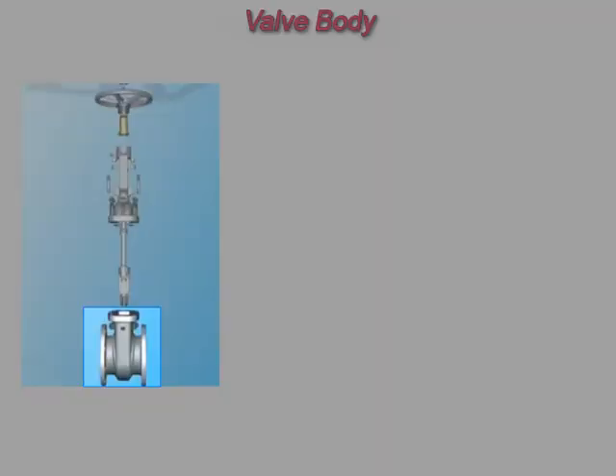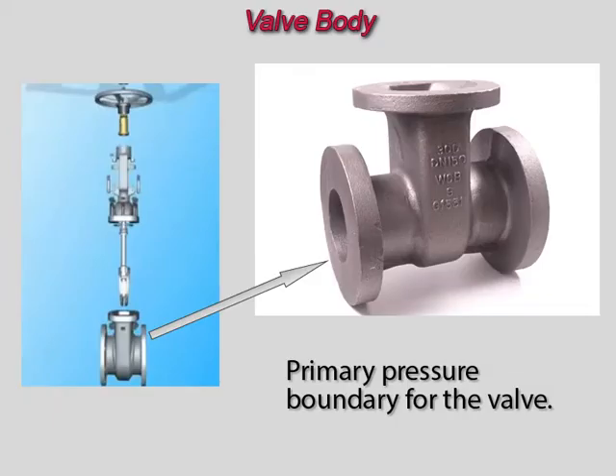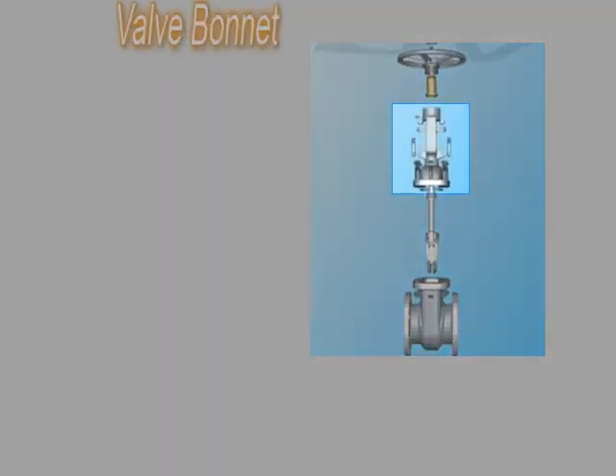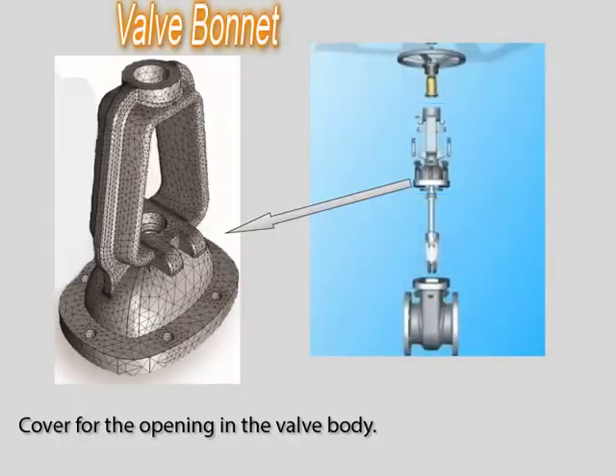The body is the primary pressure boundary of a valve. It is also the framework that holds the valve together. It houses the valve internals and provides connection points to the inlet and outlet piping. The cover for the opening of the valve body is the bonnet. Like valve bodies, bonnets vary in design. Some bonnets function as simply as valve covers, while others support valve internals and accessories such as a stem, disc, and actuator.